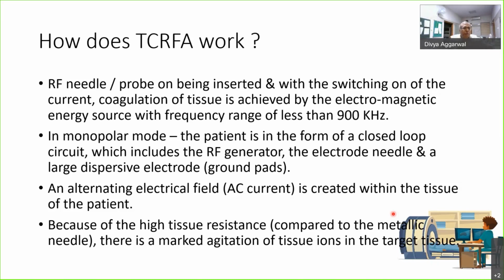So what is this closed loop circuit? It includes the RF generator, the radio frequency machine, the electrode needle, and the large dispersive electrode or the ground pads. You must have seen ground pads when using a monopolar cautery; you always place the ground pad. That makes up the circuit. So an alternating electrical field is created within the tissue of the patient. When you have inserted the needle and switched on the radio frequency, an alternating current field will be created within the tissue of the patient.